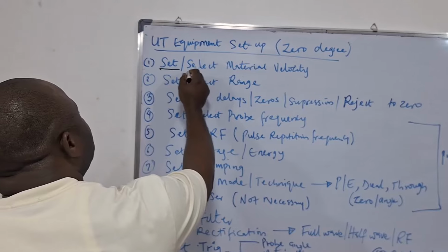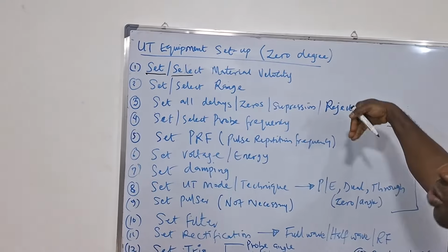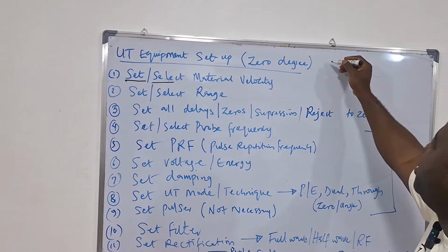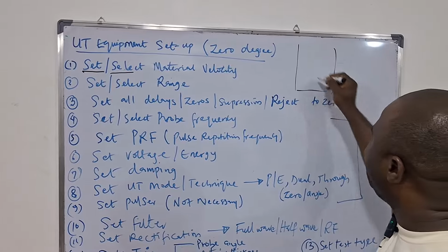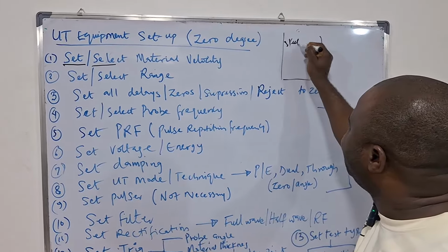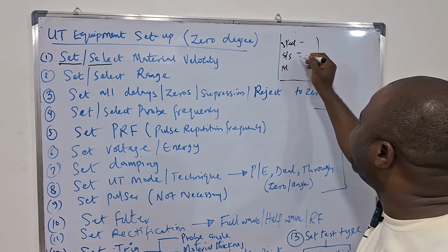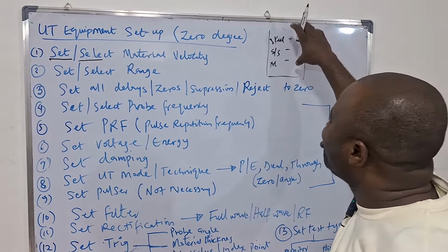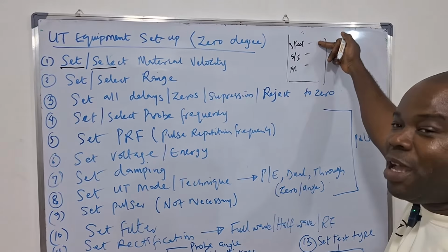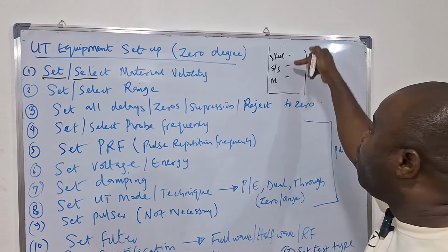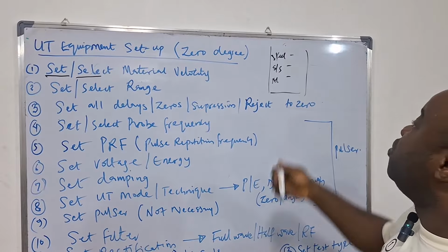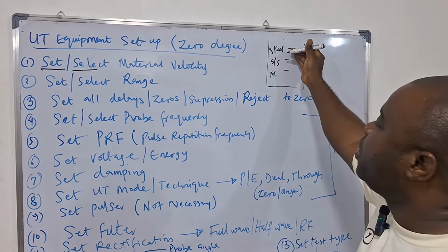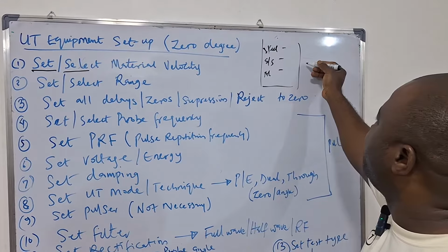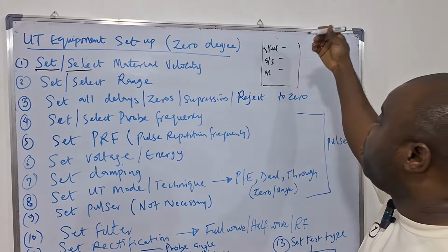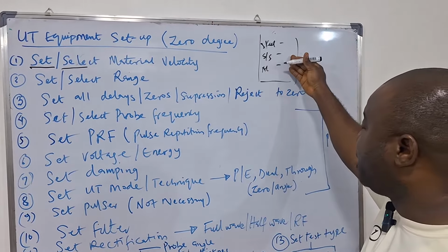Some machines give you the option of a drop-down. For example, if you look at the Sonatest series, when you go to velocity, there will be a drop-down where you see steel, stainless steel, aluminum, and so on, with the required velocity. When using such units, you just go down the drop-down menu and select the material you are actually testing. You also need to be careful, for example with steel, whether you are using shear wave or longitudinal wave. For 0-degree, you are definitely going to select longitudinal.